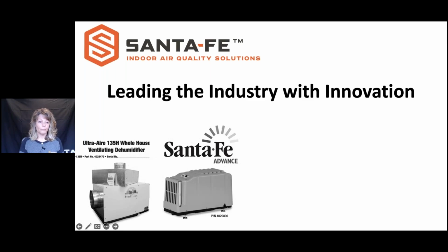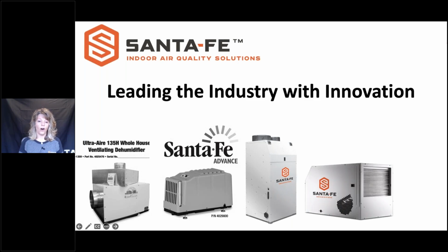We also were the first to market with the horizontal dehumidifiers for crawl spaces. We're the only ones that offer a ducted vertical unit on the market. And we also offer an XT line of dehumidifiers, which integrates a heat exchanger inside of the dehumidifier, which allows us to remove more water using less energy by getting to dew point faster.